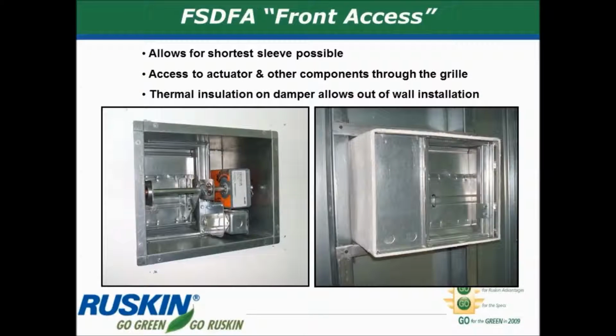And we're going to talk now about some accessories and options that are part of the life safety damper product offering. Quite often in a building, there's not the simple duct penetration from one side to the other, and it's easy to install a standard fire damper with the mounting angles. Once in a while, ductwork will terminate at the wall with a return grill, and so you can't have a sleeve protruding through both sides of the wall. And in that case, you would use a special front access or grill access damper, as shown here. These dampers terminate right at the plane of a wall, and the grill covers it up, and you can take the grill off to access the actuator motor or to service the damper.